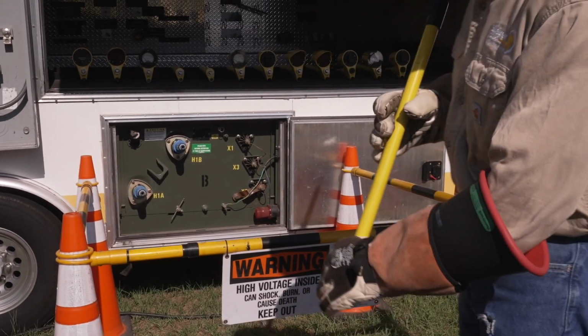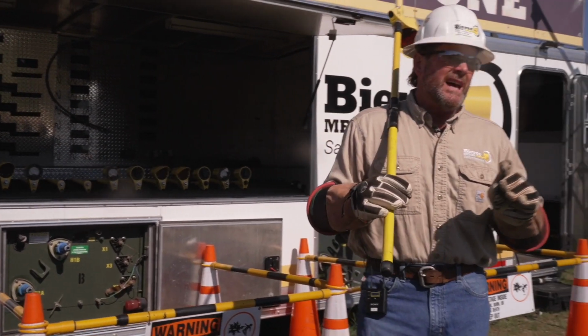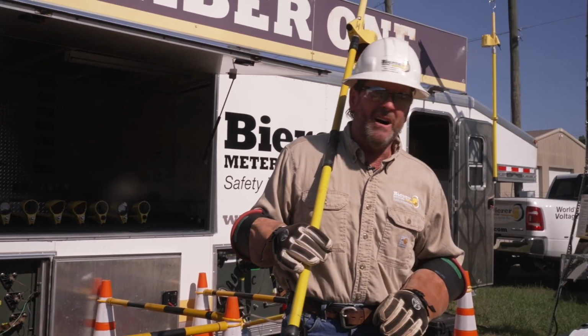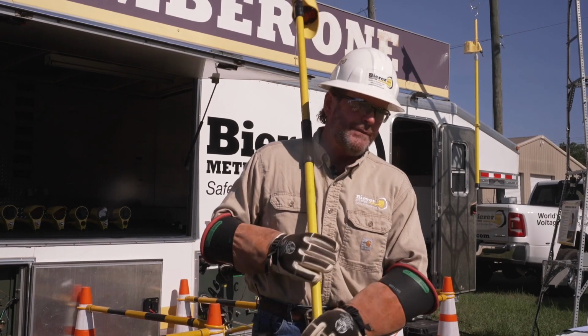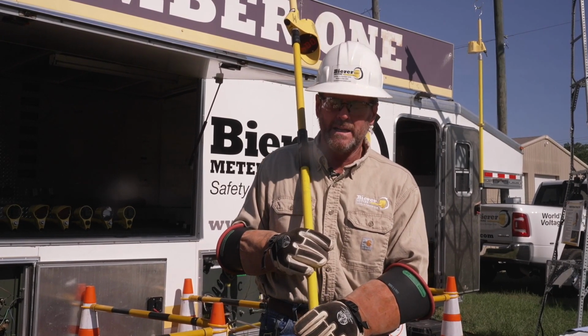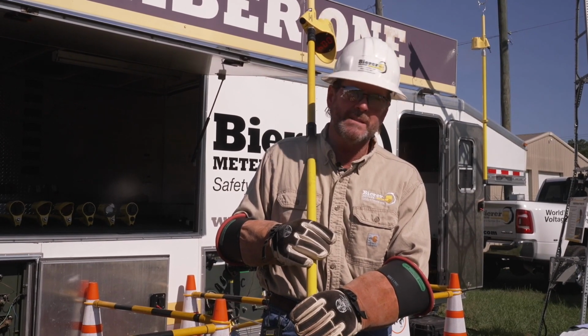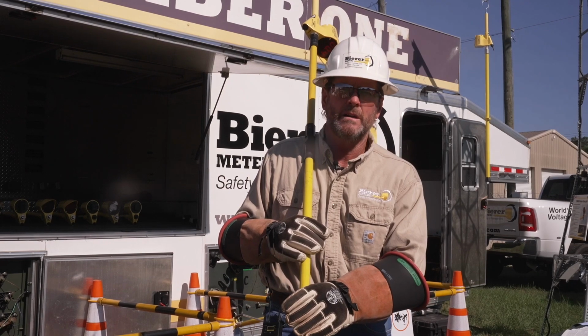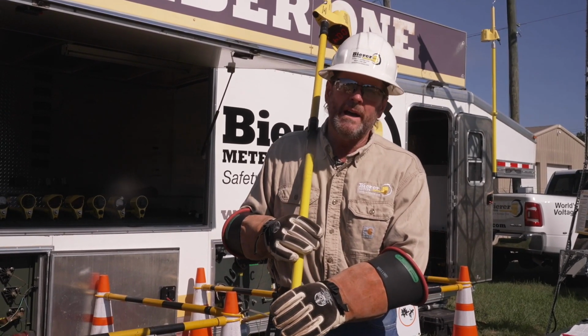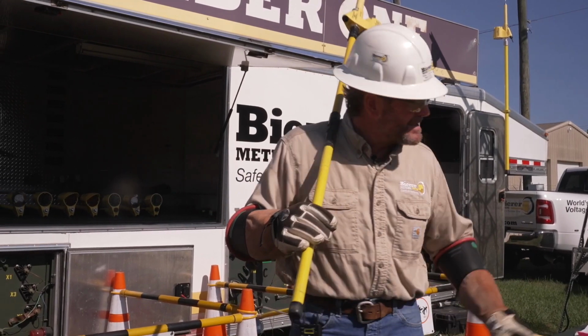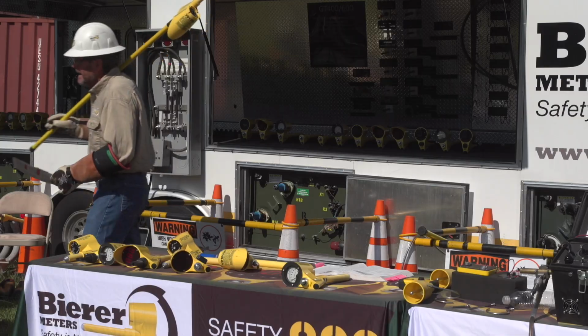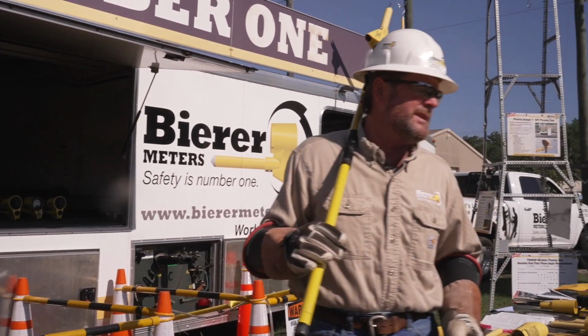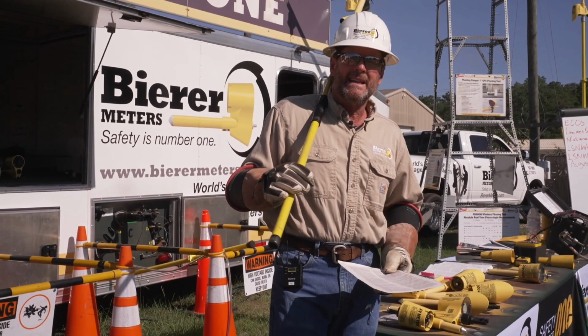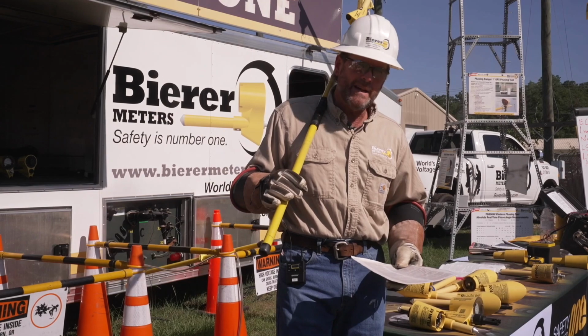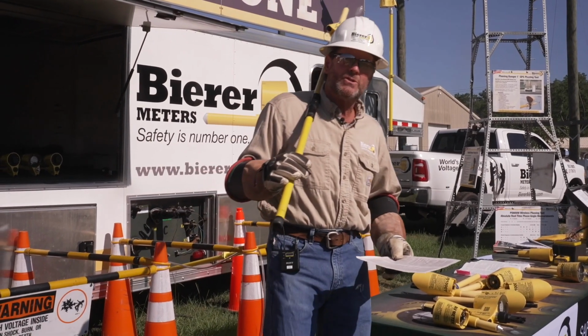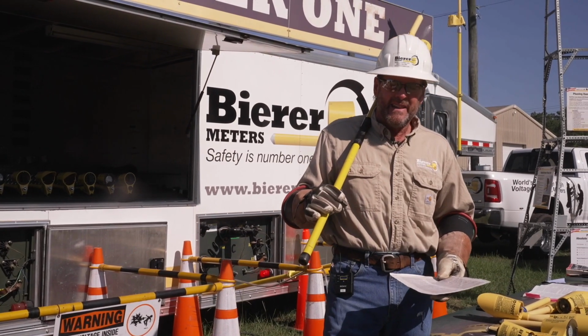Now what we're going to talk about: the P setting is very effective, but linemen don't want to use that tool, the proximity setting, to verify hot or not. If you have any non-contact tools or devices, we highly recommend you throw them away. In South Carolina we say chunk them, or chunk it - that means throw it away. The reason why is because, per 1910.269, it's going to ask you to verify prior to putting on your TPGs that you have an absence of nominal voltage. But how we like to train is we want tools accurate enough that we make direct contact, and that tool is going to give us the facts.